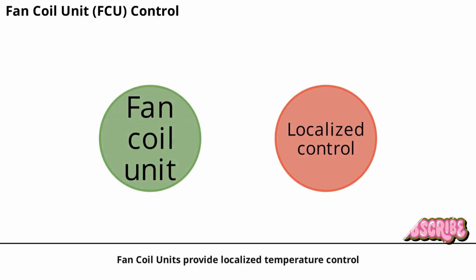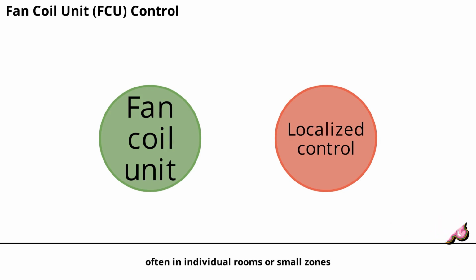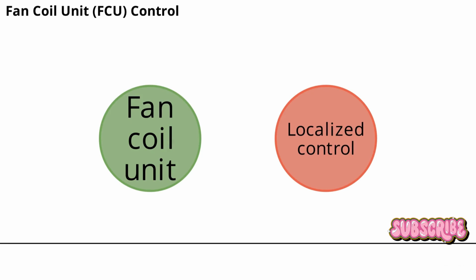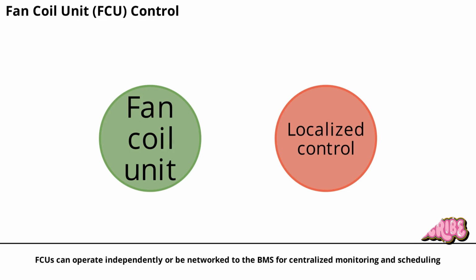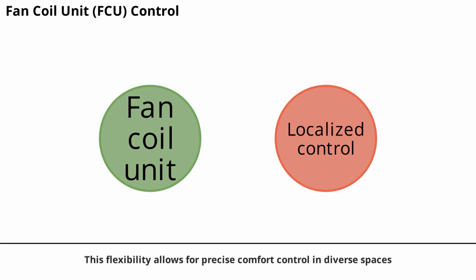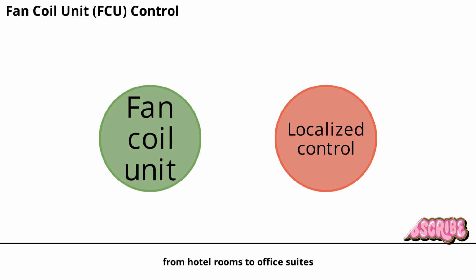Fan coil units provide localized temperature control, often in individual rooms or small zones. Each FCU uses a room thermostat, a 3-speed or modulating fan, and a 2-way or 3-way valve for chilled water. FCUs can operate independently or be networked to the BMS for centralized monitoring and scheduling. This flexibility allows for precise comfort control in diverse spaces, from hotel rooms to office suites.